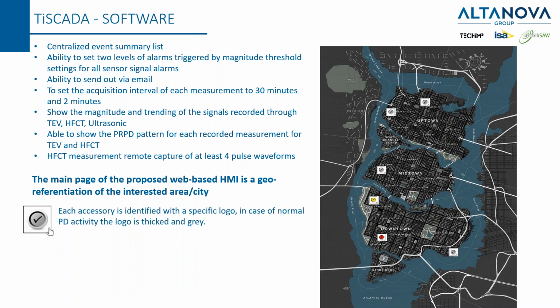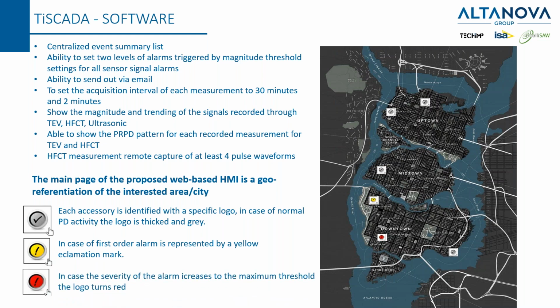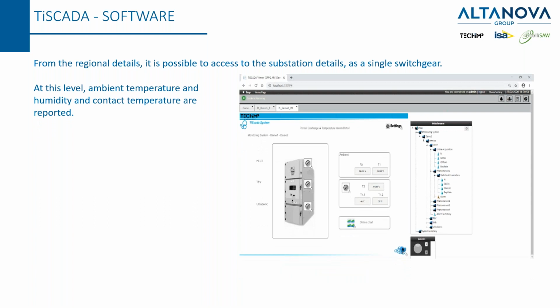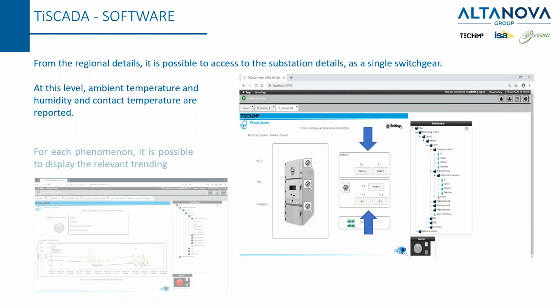Each accessory is identified with a specific logo. In the case of normal PD activity, the logo is thick and gray. In case of first order of alarm, it is represented in yellow. And of course, when it comes to critical, the color is marked as red. Moving from the regional details, I mean, from the city area main page, it is possible to access all the substation details and a single switchgear. At this level, the ambient temperature and humidity, and of course the contact temperature, are reported here. And since they are numeric values, they are immediately represented on the page.